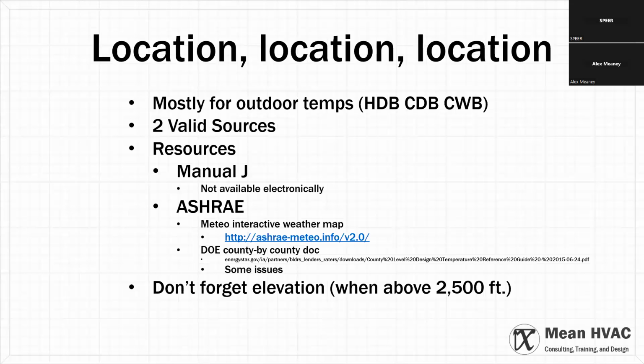The other factor, actually two other factors that the location can have an effect on, is elevation. So for West Texas, this is why I asked about West Texas. The folks in West Texas, once you get above 2,500 feet above sea level, that's the magic number. That's where you start adjusting. You're always adjusting the load if you're using software. I don't care whose software it is. If it's Manual J certified, they're using psychrometric adjustments for infiltration, ventilation, things like that. So elevation does impact the load. It's not a huge impact, but it does.